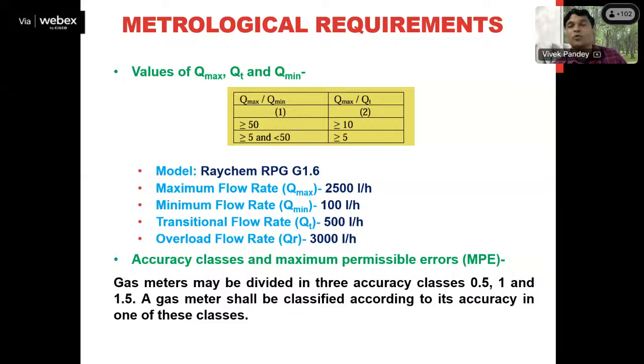Otherwise, suppose the Q maximum to Q minimum ratio is not greater than or equal to 50. Suppose it is more than 5 and less than 50, so it is between 5 and 50. In that case, the Q maximum to Q transitional ratio should be greater than or equal to 5. In our case, the maximum to minimum flow rate ratio, 2500 divided by 100, is what? It is 25. So 25 means what?